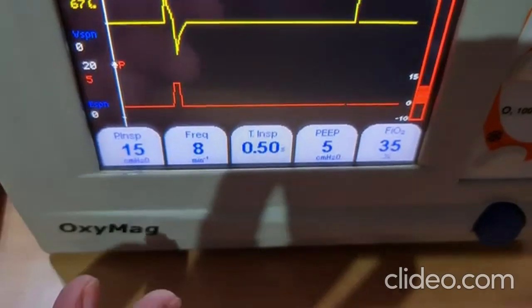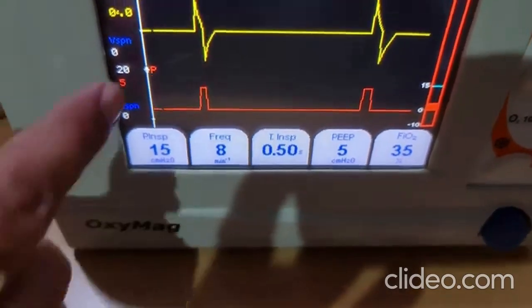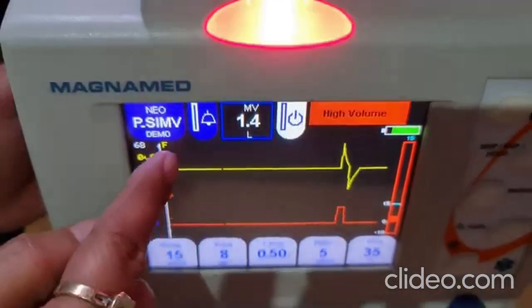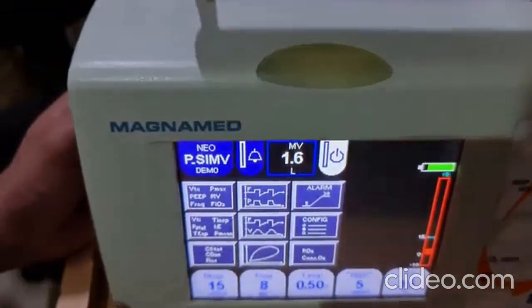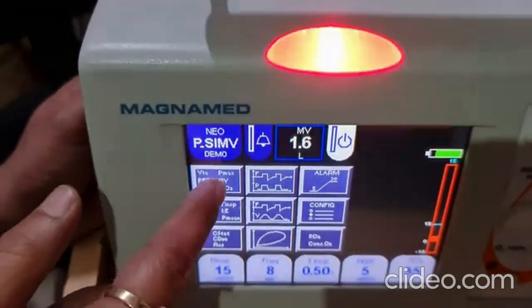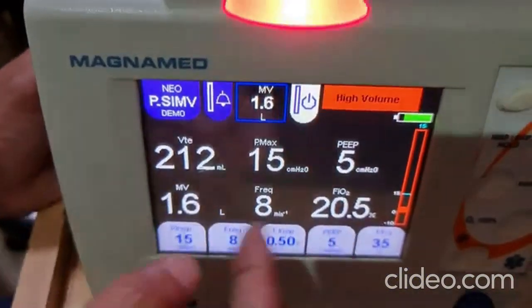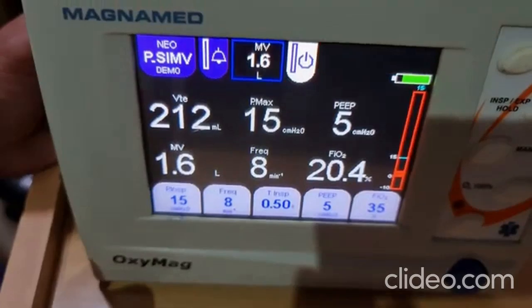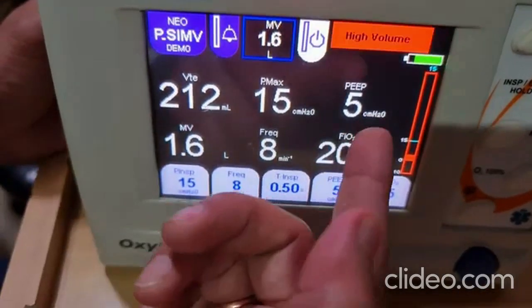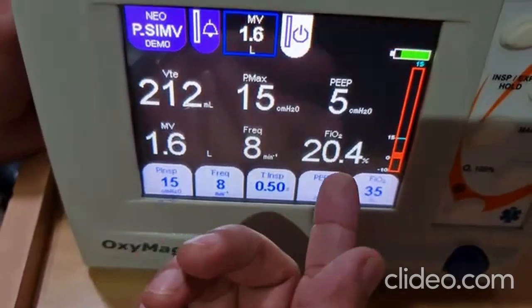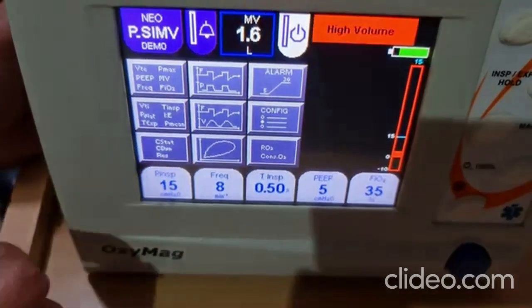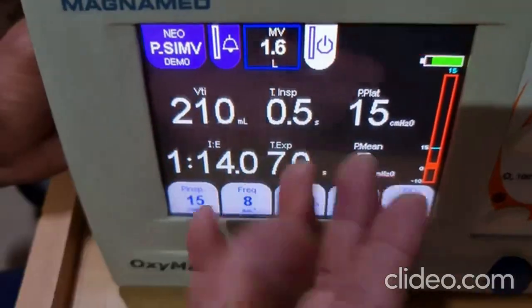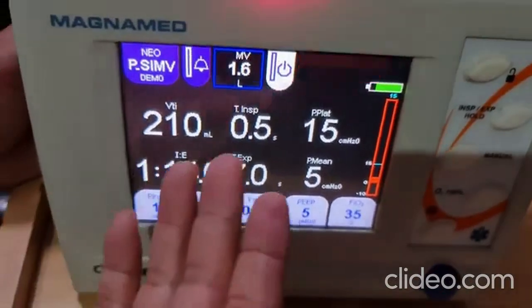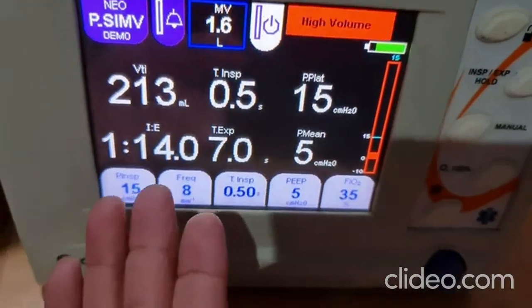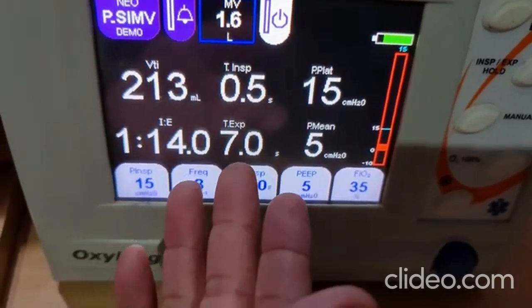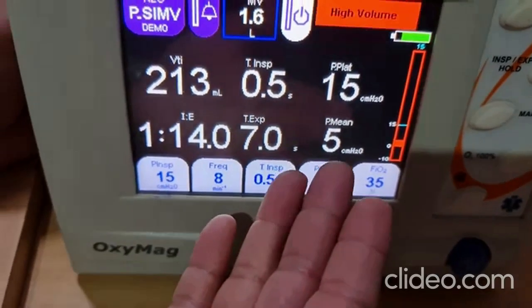Now you can monitor other things also, other parameters. Say just touch anywhere in the screen. These 9 windows will come. First window is expired parameters, numerical values you will get. This is the tidal volume, P max, minute volume, frequency, FiO2. Touch again. Second screen, this is the inspired parameters. Inspired volume, inspiratory time, plateau pressure, IE ratio, expiratory time, mean airway pressure.